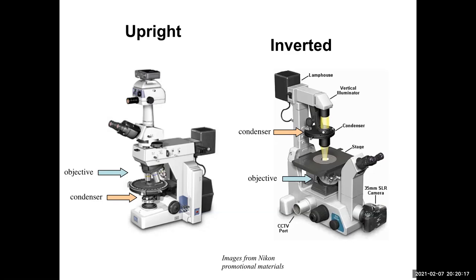The scope on the right is inverted because upright was the first design and then people invented the inverted scope. It's actually the same light path, just flipped gravity-wise: the light is at the top, goes through a condenser, through your specimen, through the objectives, and out to the oculars or camera. It's the same exact thing — just flipped over.